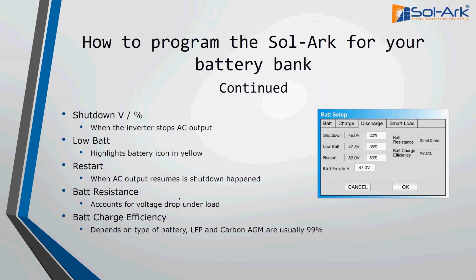And then battery charging efficiency, as I was saying before, pretty much all the batteries being used right now in solar are 99%, so you won't usually have to change that setting unless you're using a wet cell battery or something. And then arguably the most important thing on this screen is going to be the battery empty voltage. We use this for a few different things.